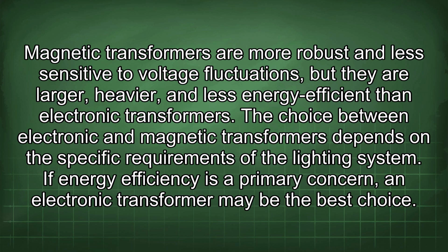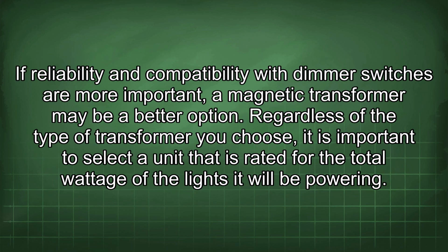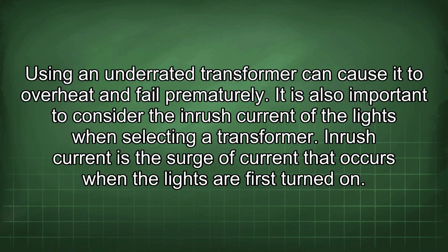If energy efficiency is a primary concern, an electronic transformer may be the best choice. If reliability and compatibility with dimmer switches are more important, a magnetic transformer may be a better option. Regardless of the type of transformer you choose, it is important to select a unit that is rated for the total wattage of the lights it will be powering. Using an underrated transformer can cause it to overheat and fail prematurely.